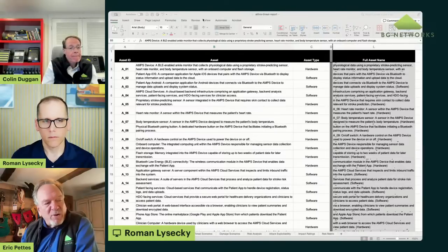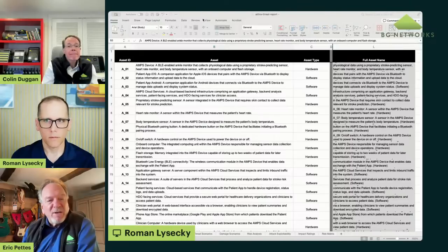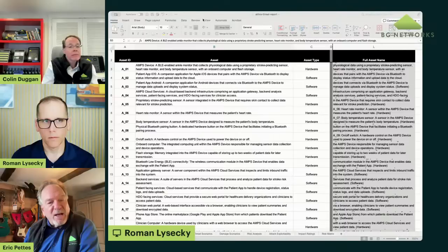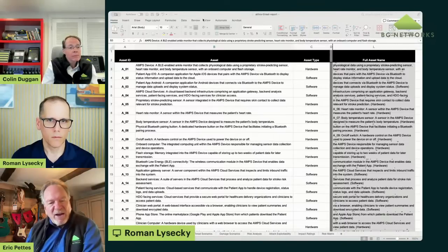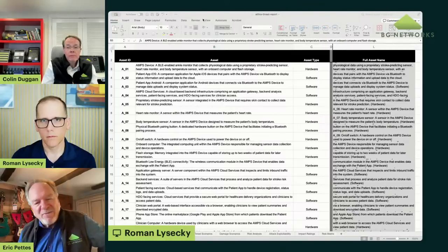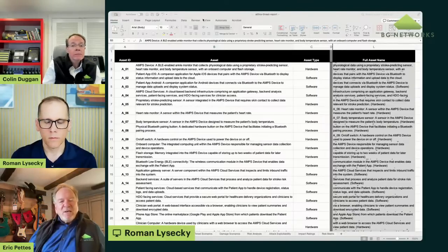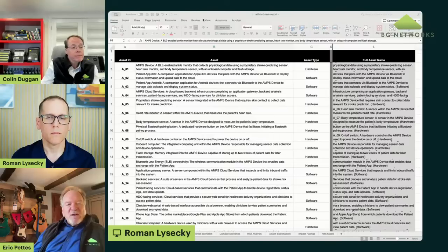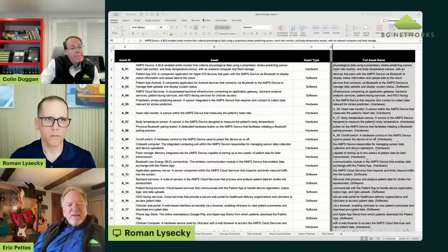Mitigations are required for anything moderate or above. We recalculate our residual risk. And then anything that's high or very high requires a risk-benefit ratio. That's going to happen on the safety side in the risk management file. And as I said before, every line item that has a safety impact, regardless of the level, will be ported over into your safety side risk management file and be dispositioned there. So it's just standard risk management.